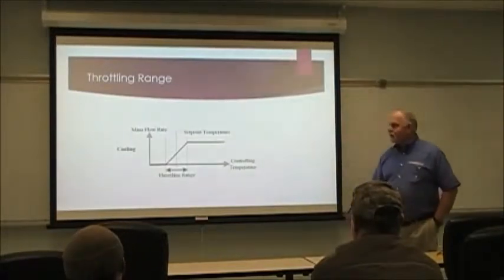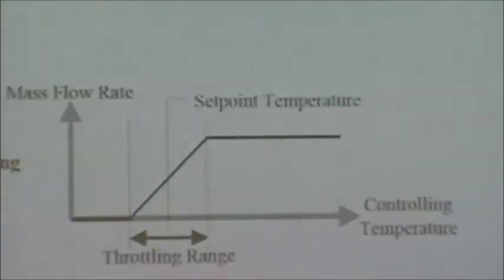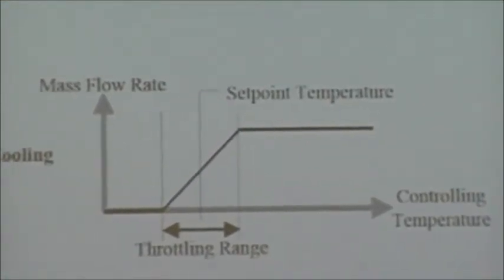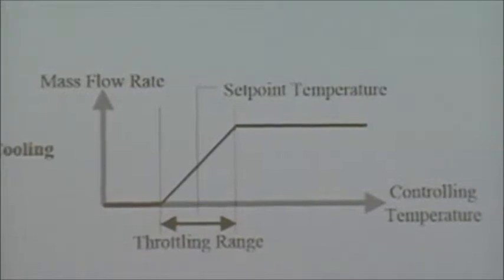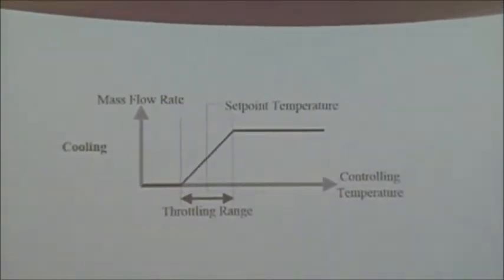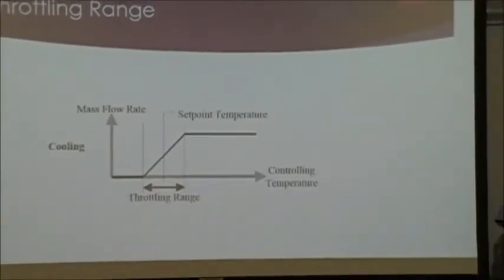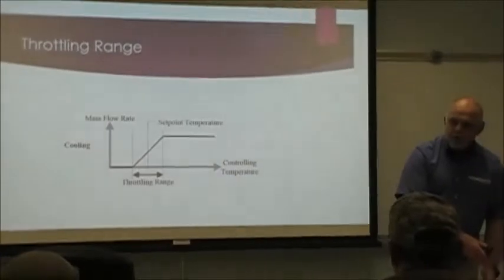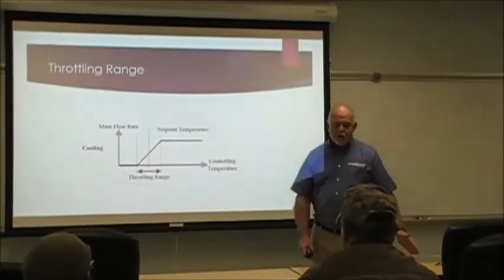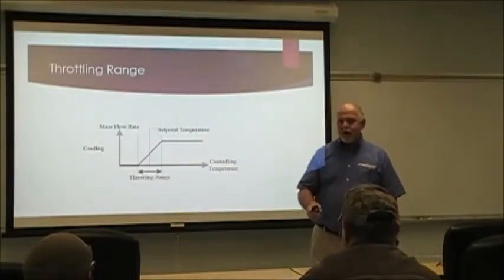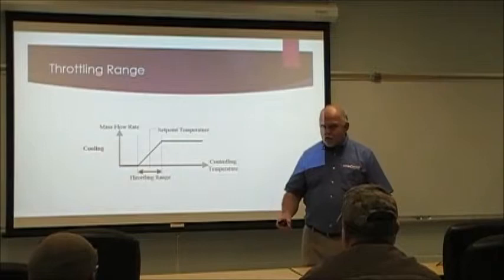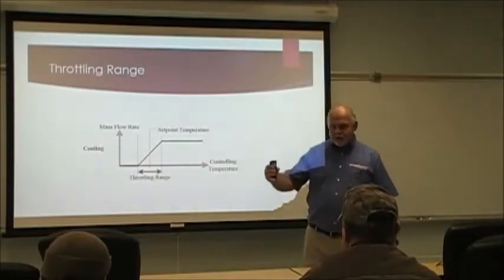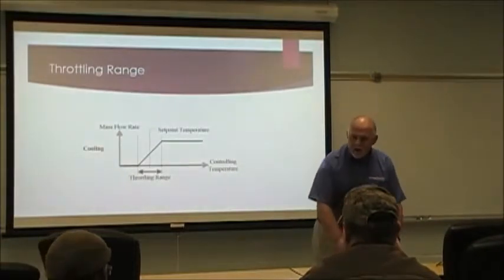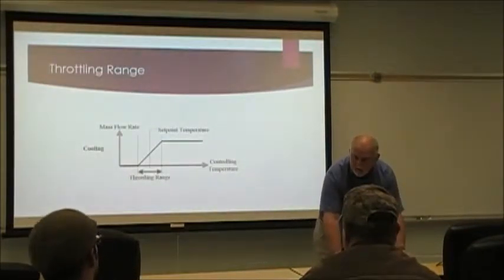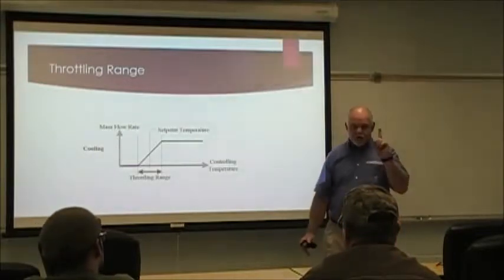Throttling range. Throttling range basically means that for a period of input, or a time or a function of input that is proportional, it goes from 0% to 100%, and that can be from 1 degree, 5 degrees, or 10 degrees. And let me explain that. If the throttling range is 1 degree, it starts at 0. We use cooling as this application. The cooling valve will be 0. It gets to that 1.1 degree, it'll be 10% open. 1.2 degrees, it will be 20% open, and so on and so forth. It'll go right on up the range just like that. Well, at that 1 degree completely there, it'll be 100% open. That means your throttling range is 1 degree.